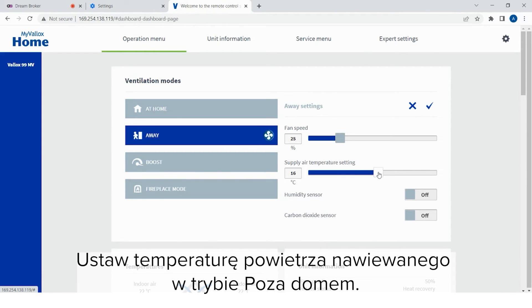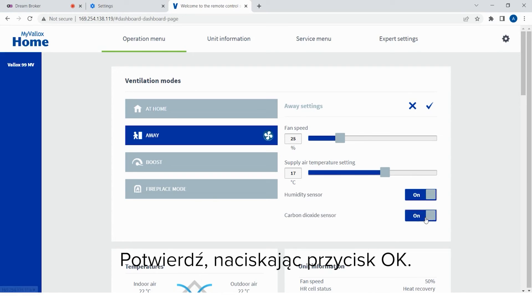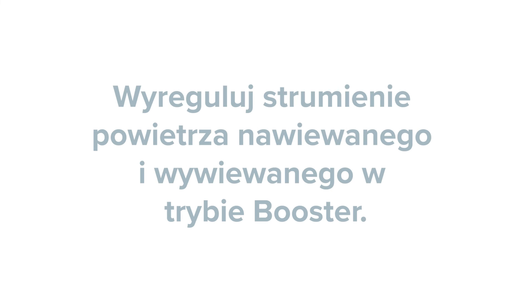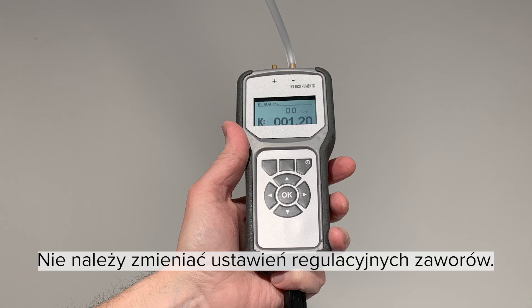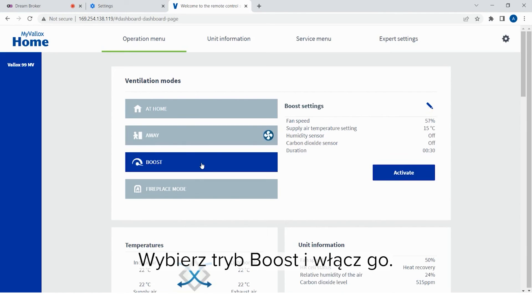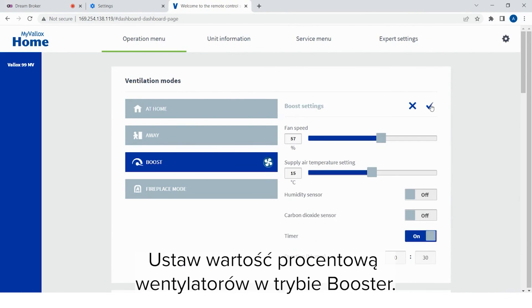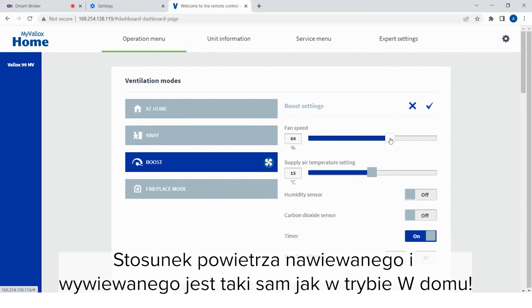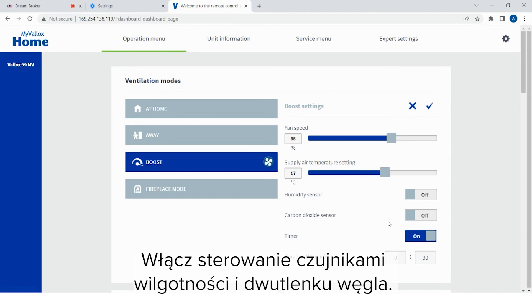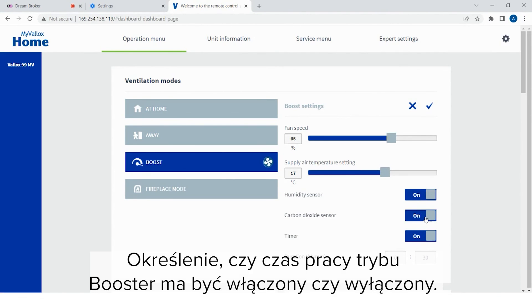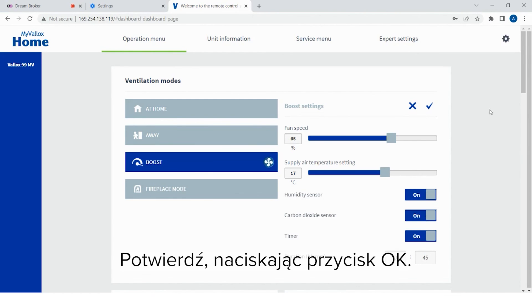Set the supply air temperature of the away mode. Turn on humidity and carbon dioxide base controls. Confirm by pressing OK. Adjust the supply and extract air flows of the boost mode. Measure the air flows from the supply and extract air valves. Do not change the adjustment settings of the air valves. Select the boost mode and turn it on. Select the boost settings by pressing the pen icon. Set the fan percentage of the boost mode. The supply and extract air ratio is the same as in the at-home mode. Set the supply air temperature of the boost mode. Turn on humidity and carbon dioxide base controls. Select whether the timing of the boost mode is turned on or off. If on, set the duration of the boost. Confirm by pressing OK.